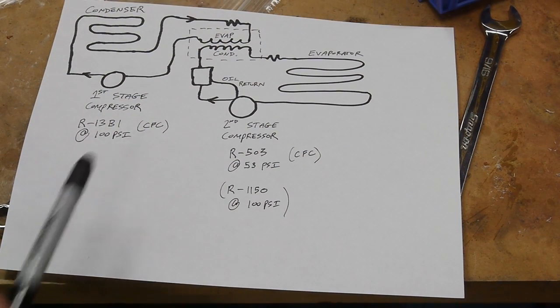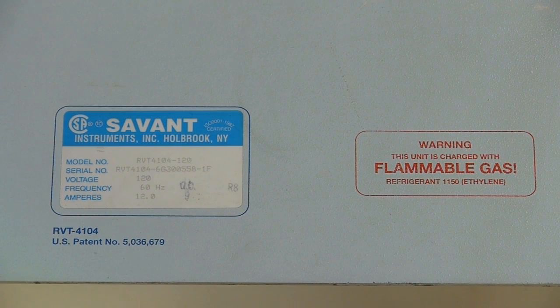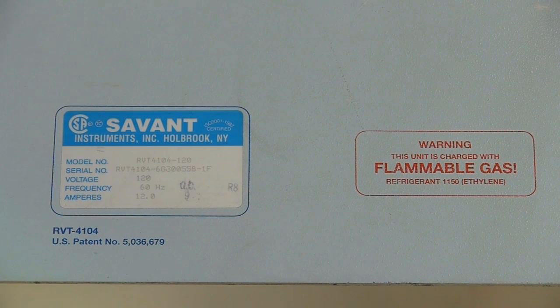The manual specced two refrigerants that should be used in the system, however there's a decal on the side of the unit that says it's charged with R1150. I'll show you in a minute that I opened the system up and found evidence that it looks like the refrigerant had been changed in it.